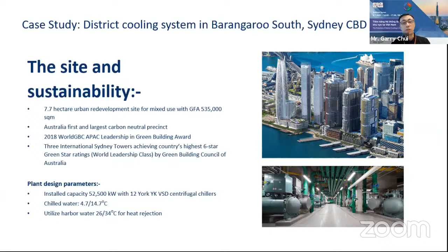There are two best practices that I would like to mention in this project. We start from the system design perspective: this district cooling system has been designed with one goal, to provide a low lift environment for the chiller to operate. So what is the so-called low lift, or what does lift mean? Because lift, in terms of centrifugal chillers, has a lot of impact on efficiency performance. What lift means, in terms of the compression of the refrigerant, is the refrigerant pressure differential that the centrifugal compressor has to overcome.